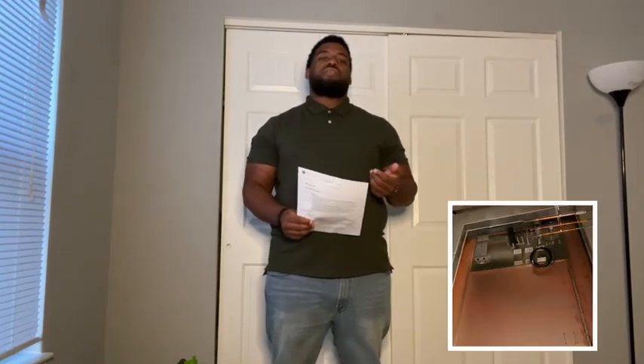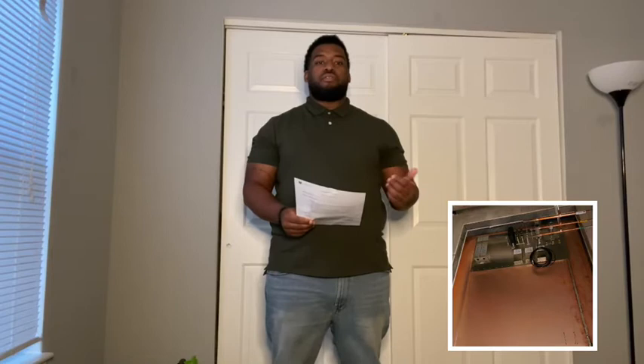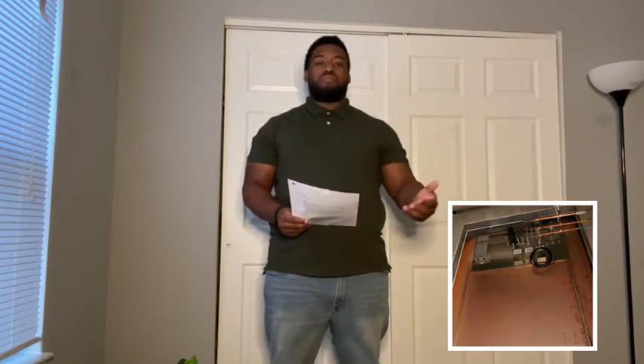When dealing with your medical gases, you have to determine a specific size that's going to run into the room just because you have to provide a waveguide for that as well. When dealing with lighting, you're not doing your typical can lights either. These have to be MRI approved lighting. With each MRI approved lighting brand, there comes a certain number of filters that are needed per circuit or a certain number of filters that are provided with the lighting that you purchase.